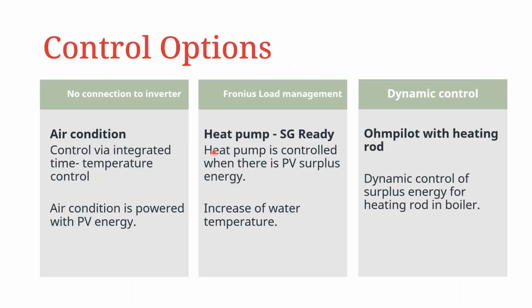So control options, we already covered this, so there's no need to go through them again, but you have the possibility to do a control without a connection to the inverter. You have Fronius load management, whereby a connection is required using the digital IOs, and then a dynamic control of the surplus using something like Wattpilot or Ohmpilot.